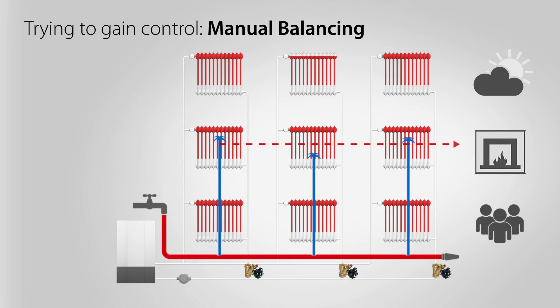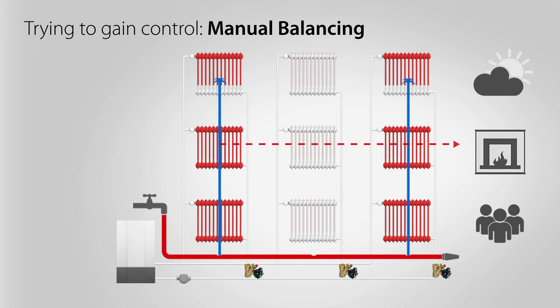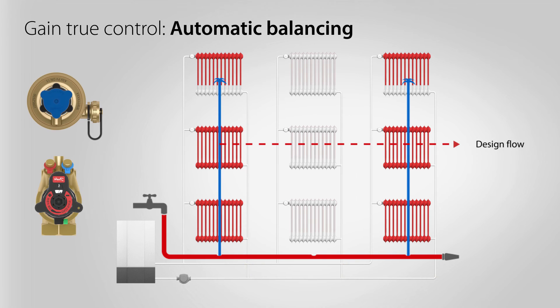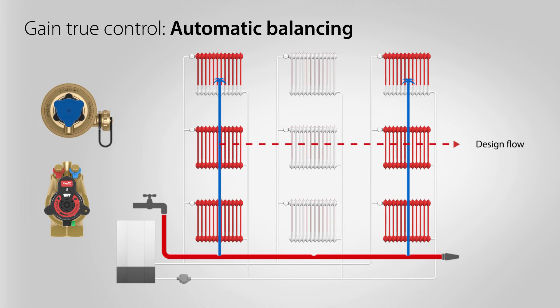A heating system becomes a variable flow system when partial load conditions occur. The supposedly balanced system will again have poor balance and water distribution. Manual balancing valves are not the correct choice to gain control. To really solve the hydronic challenges, an automatic balancing solution with differential pressure control is required.